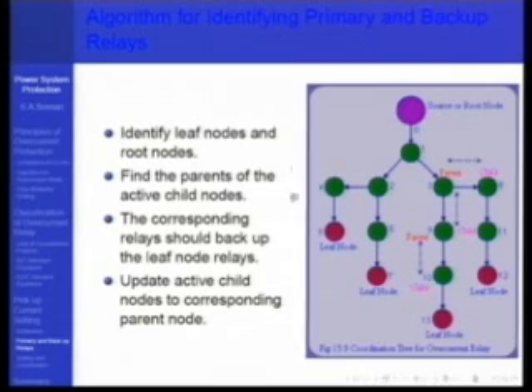So to do the TMS setting, you will do it first at the leaf nodes, because these relays don't have to coordinate with any other relays. Therefore their time multiplier setting can be set to minimum, because protection should always be as fast as it can be. Then you look at the relays which are backing them up, the parent ones, as I call them in this figure. Then you slow these relays down by the coordination time interval. And then you go back further. These first leaf nodes, then the relays which are backing them, then the relays which are backing those up, until you reach the source. So you start from the leaf nodes and do coordination and try to reach the source node.